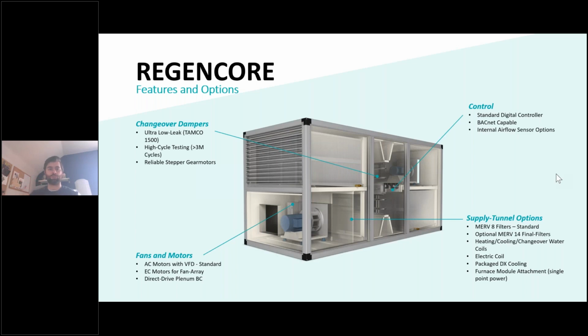But on all RegenCores, we've standardized around the low leak Tamco 1500 dampers. We high cycle tested those, so changing every second, so a swap every second within our factory for 9 months without failure, which simulates, I believe, somewhere between 7 to 10 years of operation, depending on your cycle timing. So we're very confident in our current linkage assembly and gear motors that we're using.